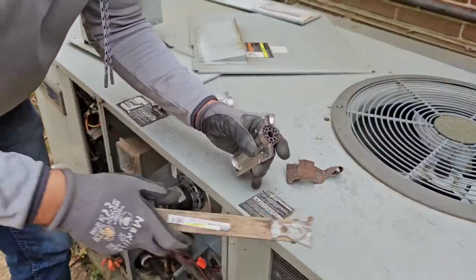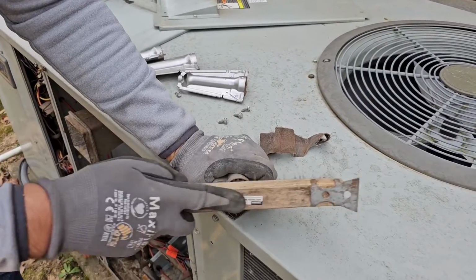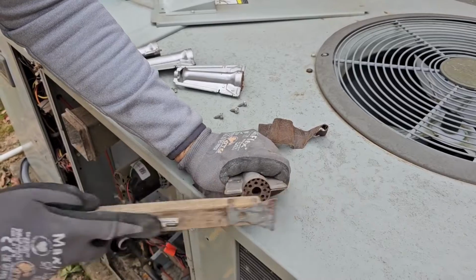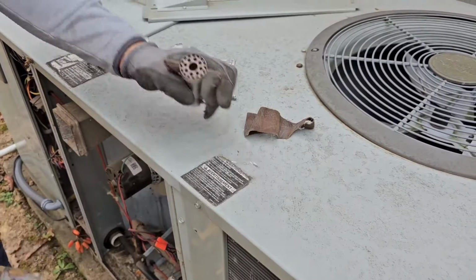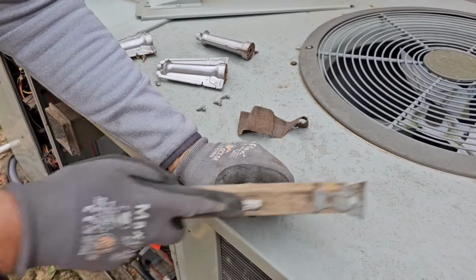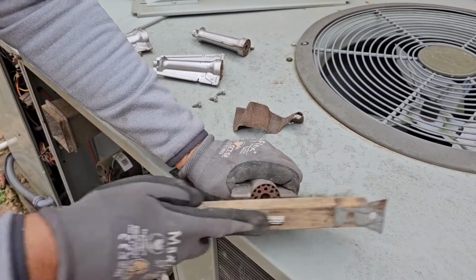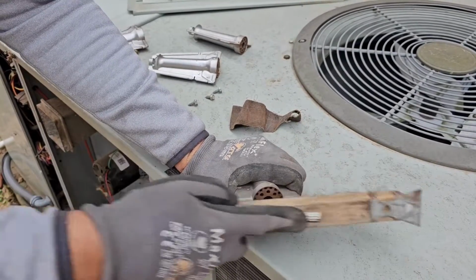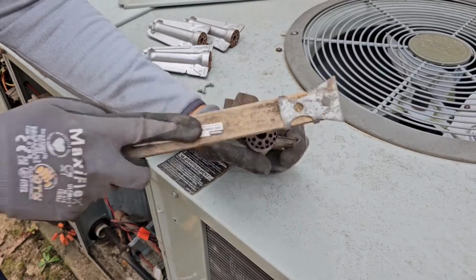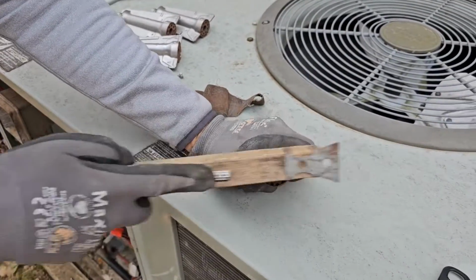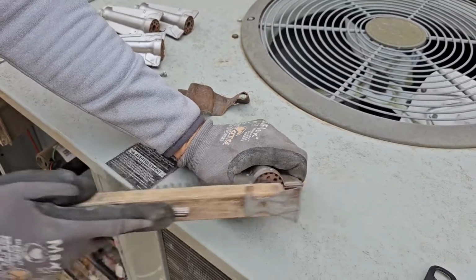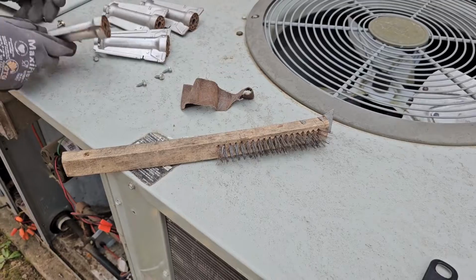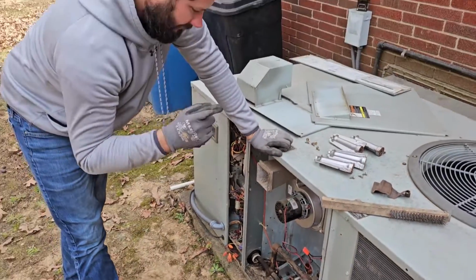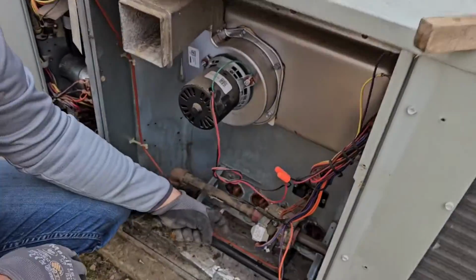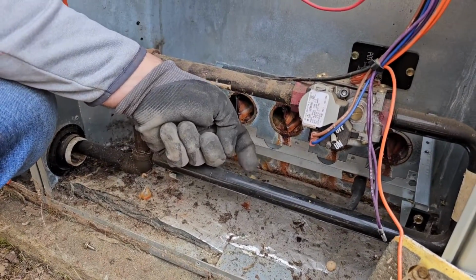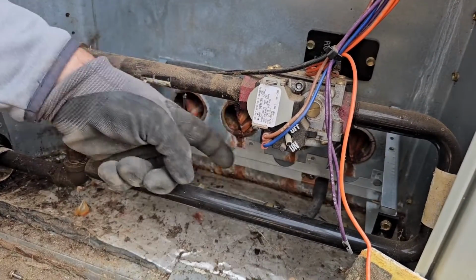So it doesn't take long to do some maintenance for a package unit, but you got to do it. And this keeps that track, the flame carryover track, clean, so that your burners all have a nice flame. And then your flame sensor detects the flame, sends a signal back to the board, and your unit works. So now, one thing you can do if it's not lighting well is you can take a little bitty Allen tool and you can stick it inside of these burners, right? I'm sorry, not burners, orifices.